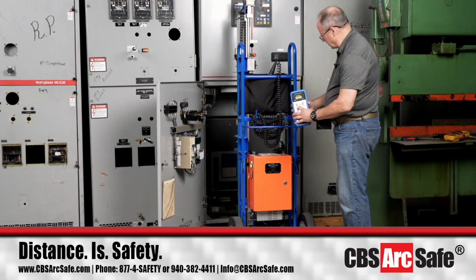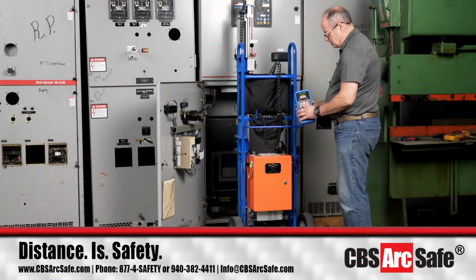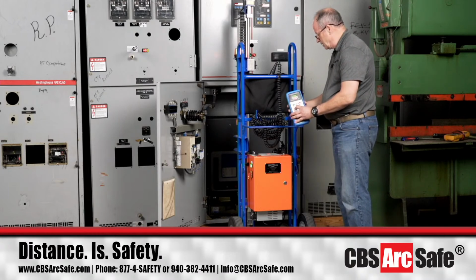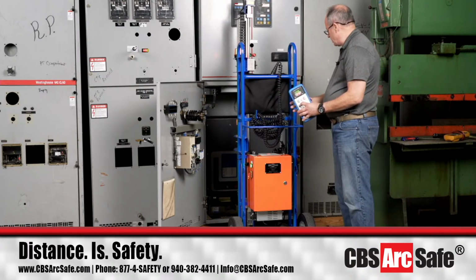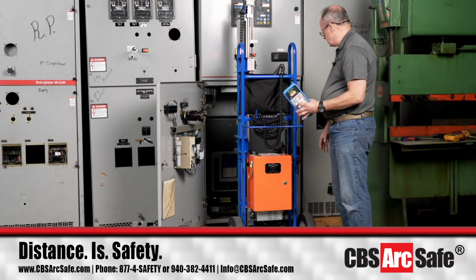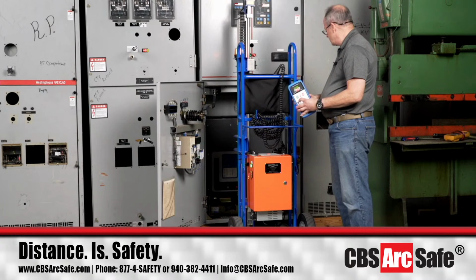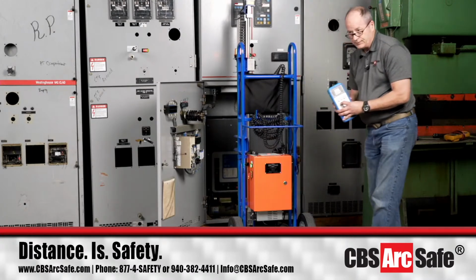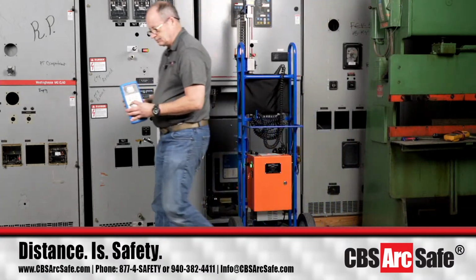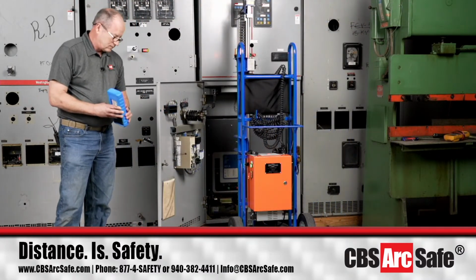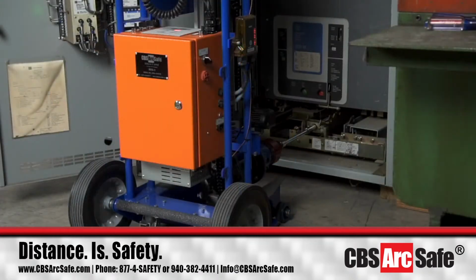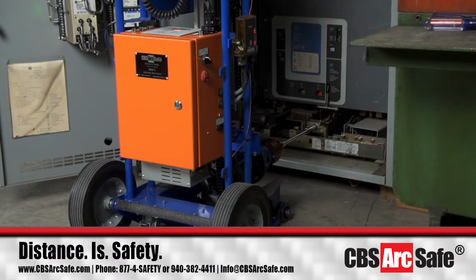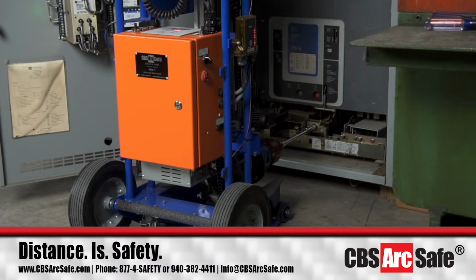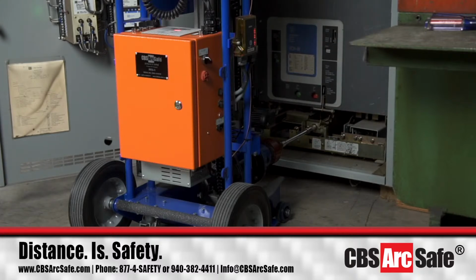So all I'm going to do now, I've got the unit hooked up. We're in the connected position, so now I'm just going to hold down remove. 5.7 is our peak, 6.6. Once the breaker comes off the bus, that peak number actually goes down in terms of how much force is being used. It takes about a minute to rack a VCP-W breaker because it's around 59 to 60 turns on the screw for the system to rack the breaker.